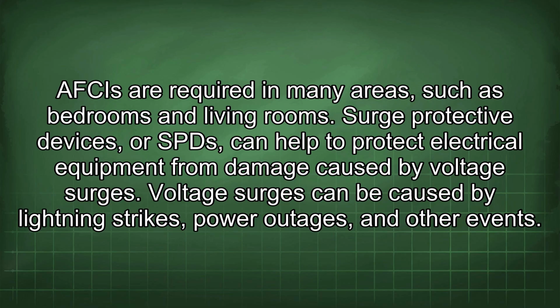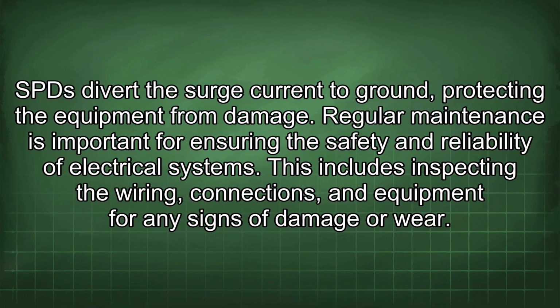Surge protective devices, or SPDs, can help to protect electrical equipment from damage caused by voltage surges. Voltage surges can be caused by lightning strikes, power outages, and other events. SPDs divert the surge current to ground, protecting the equipment from damage. Regular maintenance is important for ensuring the safety and reliability of electrical systems. This includes inspecting the wiring, connections, and equipment for any signs of damage or wear.